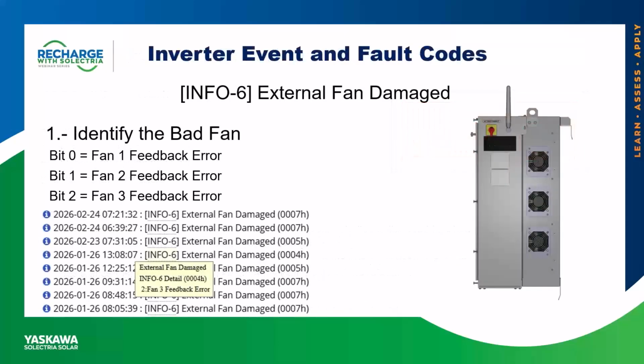And this leads us to our last common fault code that you may encounter on the XGI 1500 inverters. And that's going to be Info 6, external fan damaged. As its name says, it's pretty straightforward. There's a fan that is not functioning properly or has failed. So again, as we've been going through these slides, first we need to identify what fan has failed. So we head over to our events and fault logs, we hover over the fault code that we're getting, and as you can see in the picture, it says fan 3 feedback error.